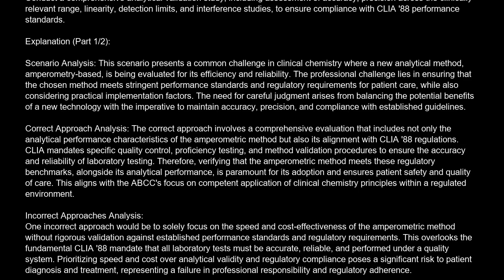Correct answer is C. Conduct a comprehensive analytical validation study, including assessment of accuracy, precision across the clinically relevant range, linearity, detection limits, and interference studies, to ensure compliance with CLIA 88 performance standards.